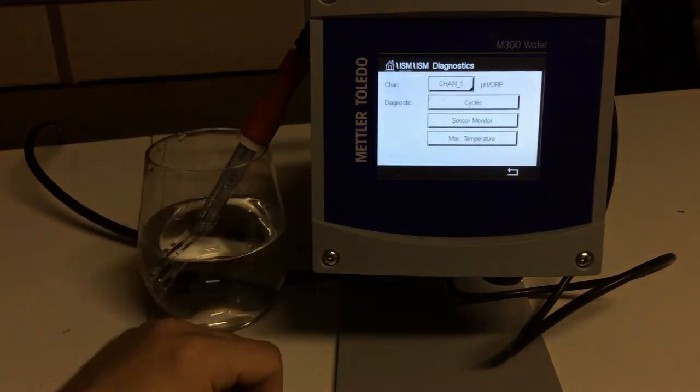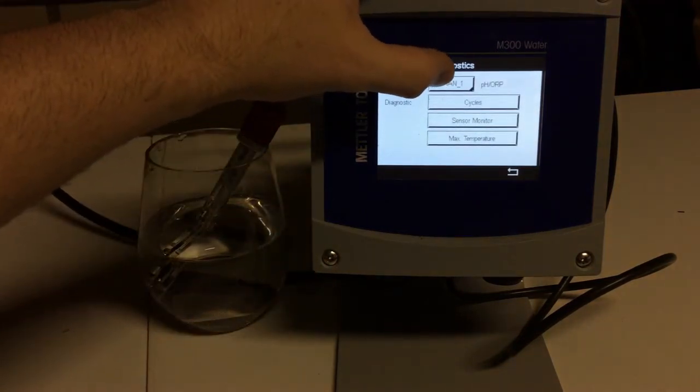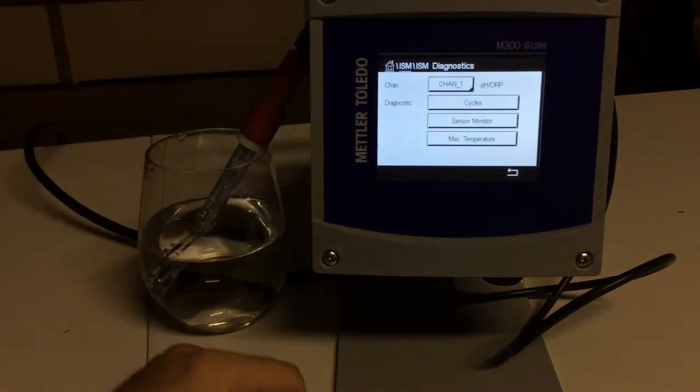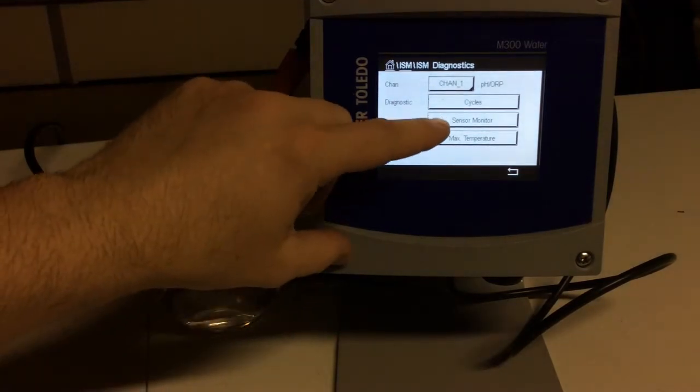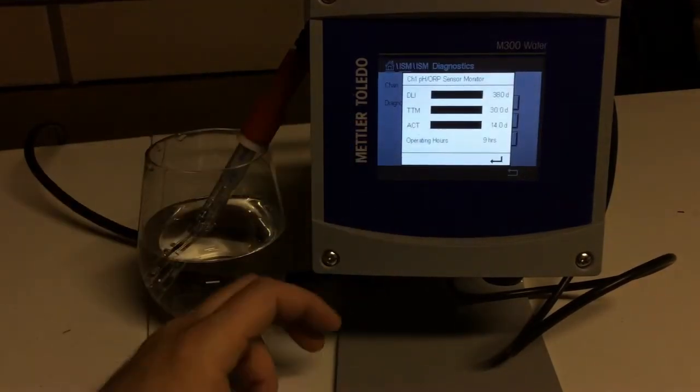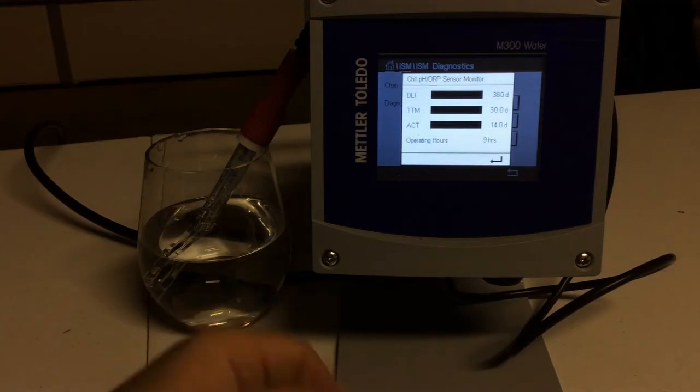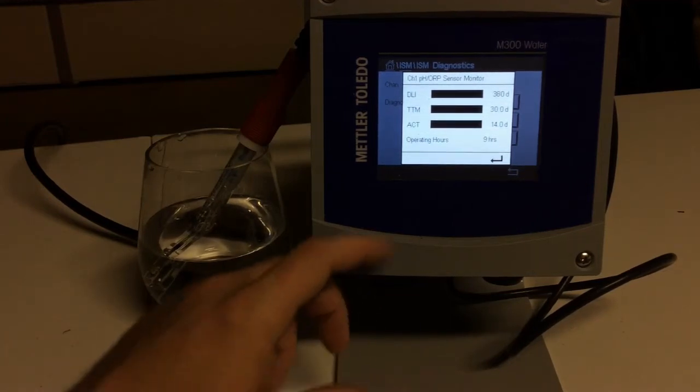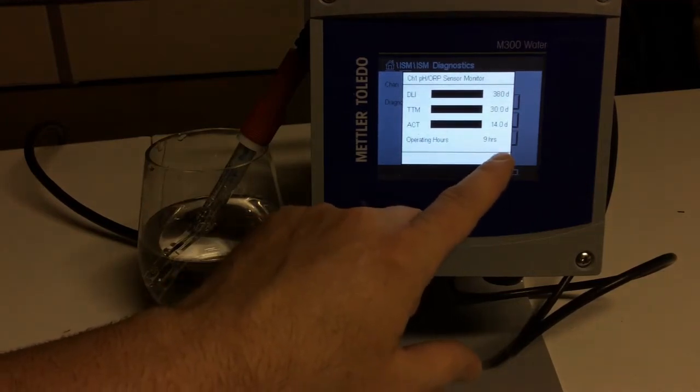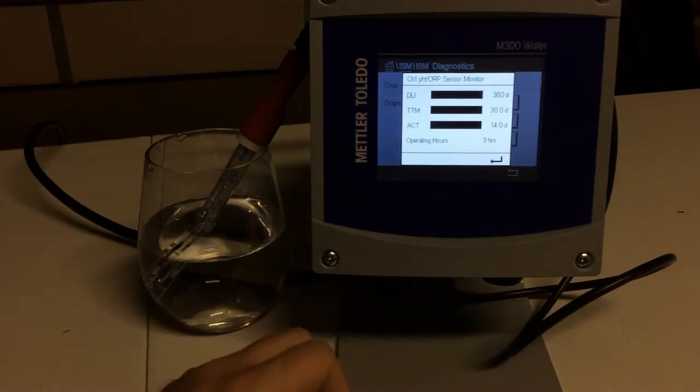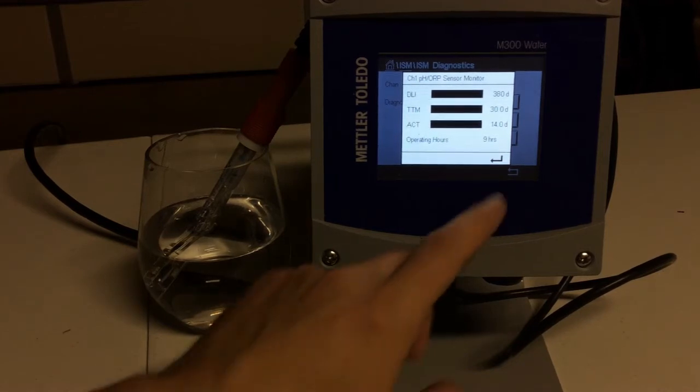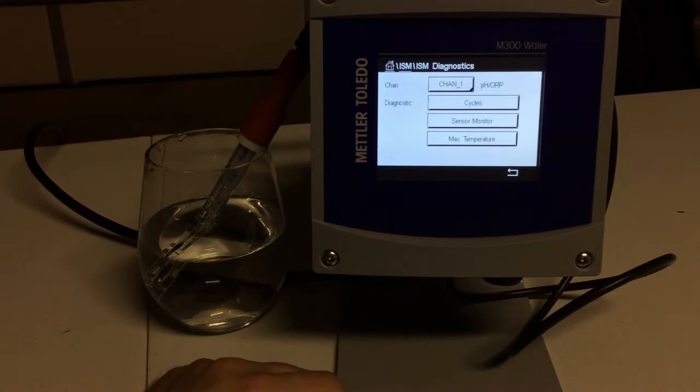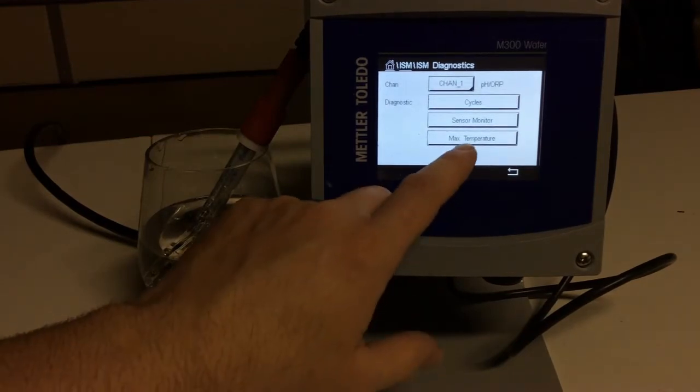ISM Diagnostics, this is a two-channel transmitter, but I only have one hooked up, so I can only see channel one. If we wanted to see sensor monitor, we'd just see the same thing that we saw with our lifetime indicator, maintenance timer, calibration timer. But, it also adds hours of operation, and we can see that this sensor has only been used for nine hours. It's a nice way for you to know how long that sensor has been in service, because I get questions all the time of folks saying, you know, how do I know, and this gives you the exact time.